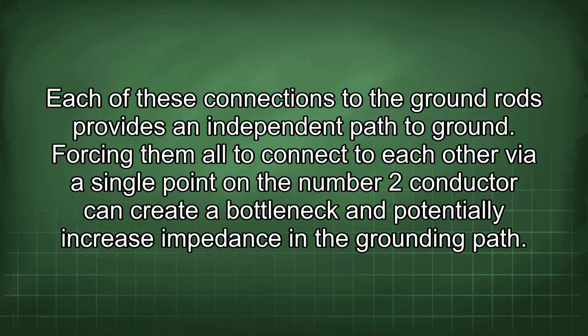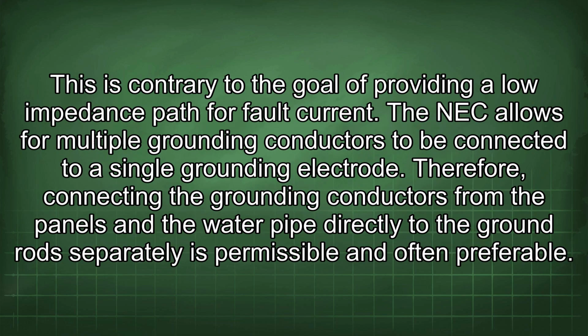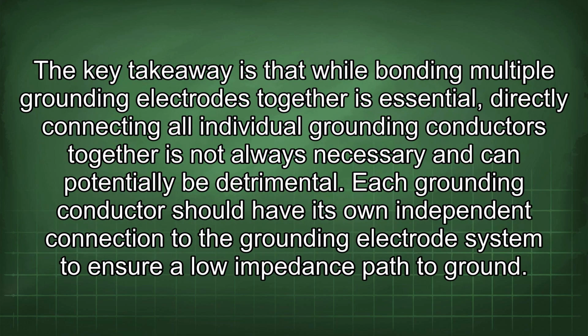Forcing them all to connect to each other via a single point on the number 2 conductor can create a bottleneck and potentially increase impedance in the grounding path. This is contrary to the goal of providing a low impedance path for fault current. The NEC allows for multiple grounding conductors to be connected to a single grounding electrode. Therefore, connecting the grounding conductors from the panels and the water pipe directly to the ground rods separately is permissible and often preferable. The key takeaway is that while bonding multiple grounding electrodes together is essential, directly connecting all individual grounding conductors together is not always necessary and can potentially be detrimental.